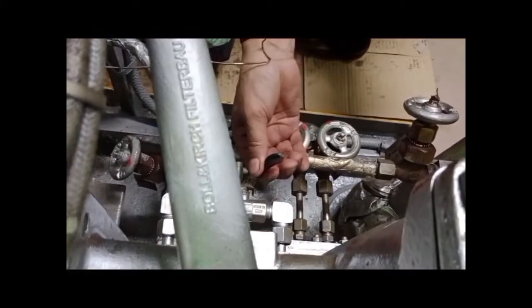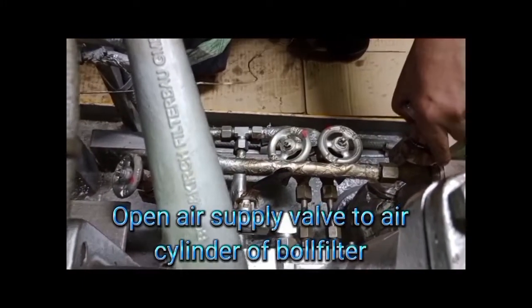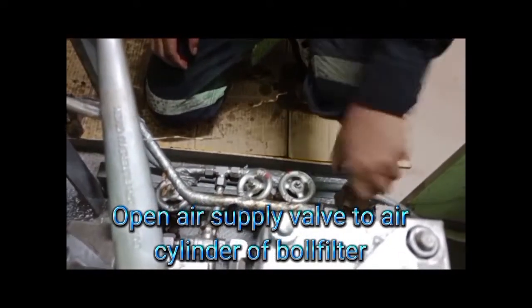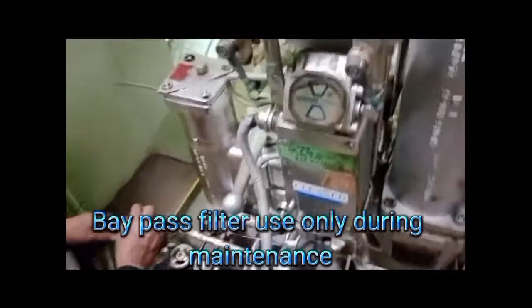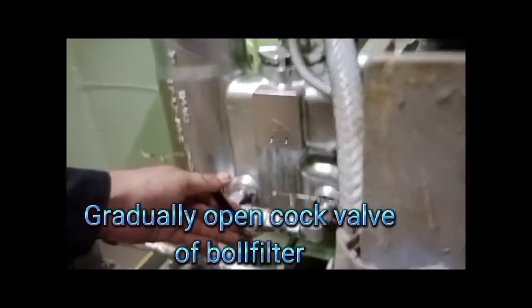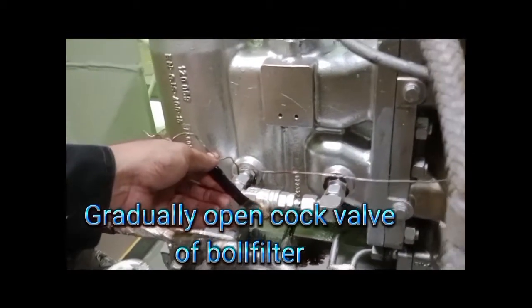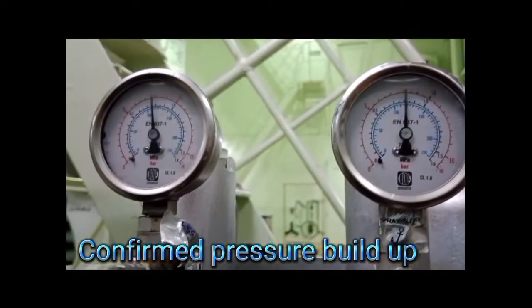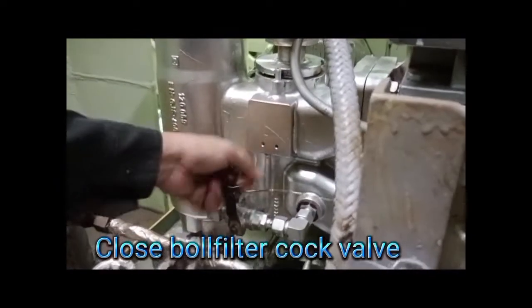Use the cock valve for priming the Bollfilter. Crack open the cock valve to prime the Bollfilter, then open the air supply valve to the air cylinder of the Bollfilter. Note: the bypass filter is used only during maintenance. Gradually open the cock valve for the Bollfilter and confirm pressure build-up on the pressure gauge. Then close the Bollfilter cock valve.